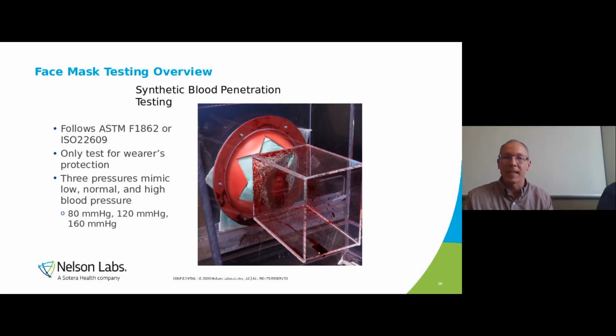The next aspect is synthetic blood penetration testing. This follows, for the US, ASTM F1862, or in Europe, ISO 22609. This is a test that tests the outside of the mask. For the other tests for face masks, we test the inside of the face mask because it's the environment we're protecting. This test, we're actually testing the outside because during surgery, if an artery were cut and blood were to spray or splatter, if it impacts that mask, we don't want it to penetrate through.